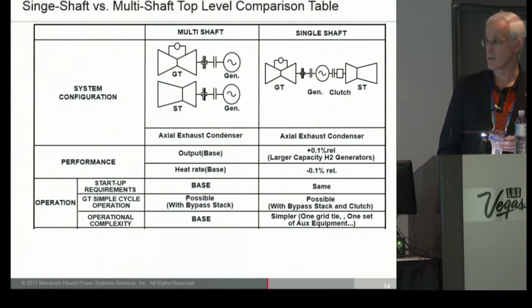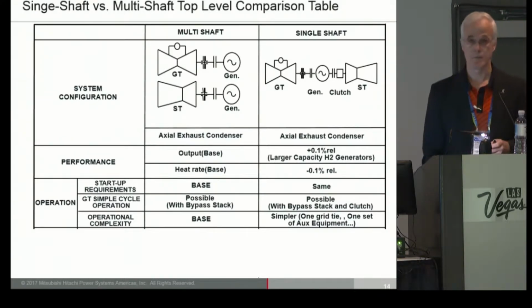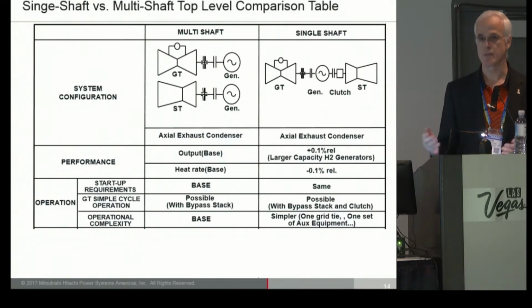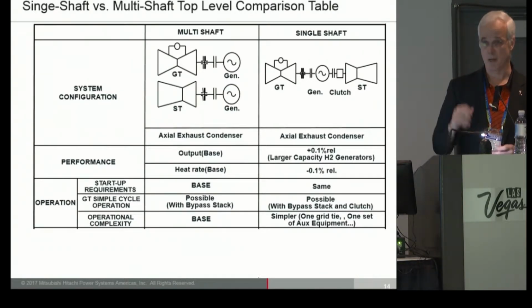Looking at operational characteristics, startups with the clutched system as this single shaft has, there really is no difference on startup time or requirements for starting. Simple cycle operation is capable with bypass stack on a single shaft. Operational flexibility or complexity is arguable both ways, but single shafts have the advantage of only having one generator synchronized to the grid, and a lot less auxiliary equipment since many systems are combined, making things simpler overall.